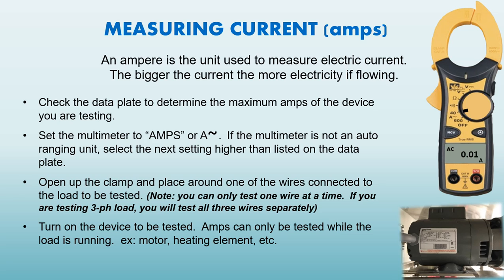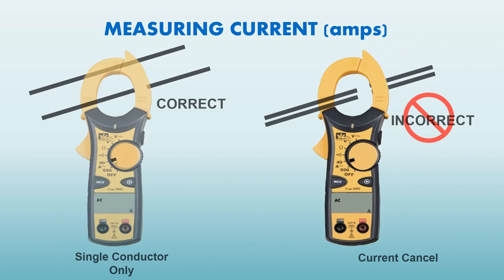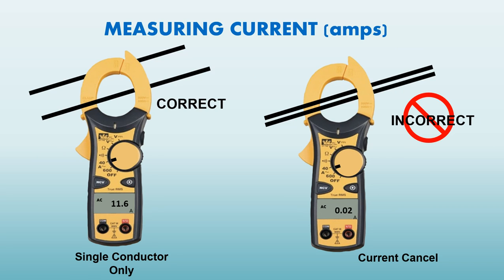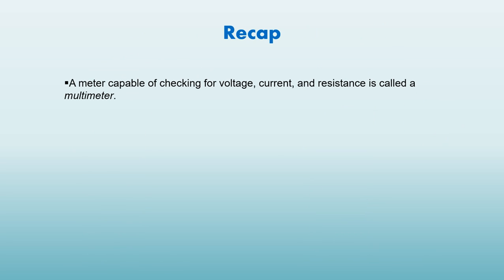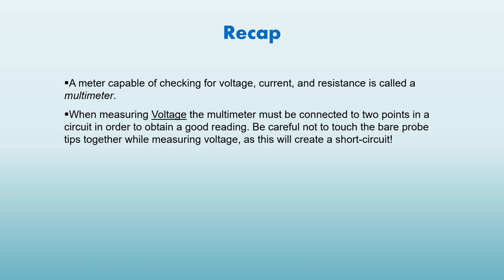One is either the motor or the heating elements are starting to go bad, or you have loose wires. Any loose connections can cause a load to try to draw more current through, which would cause the amperage to increase. If this went on for any length of time, the wires start heating up, they start becoming more loose, and eventually can either break or burn. Again, correct connections for using amps. If you're testing amperage, your meter, your jaw clamp, would go around one wire at a time. Putting it around two wires is incorrect, and you will not get a correct reading.